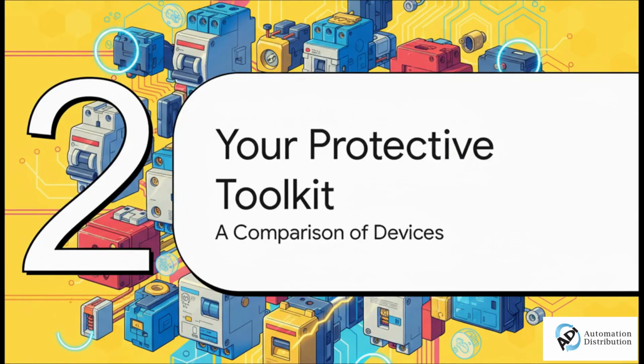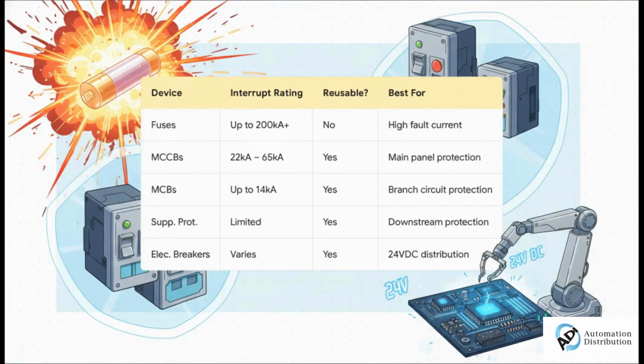Okay, so now that we know the threats, let's look at the tools we have to fight them. Think of this as opening up the essential toolkit for any panel builder or design engineer. Each one of these has a very specific job to do. So, this table here lays out our main players. Right off the bat, you'll notice fuses have an absolutely incredible interrupt rating, which makes them perfect for places where you could have a really high fault current. Then you've got your workhorses, the big molded case circuit breakers, or MCCBs, for your main incoming power, and the smaller miniature circuit breakers, or MCBs, for all your individual circuits.